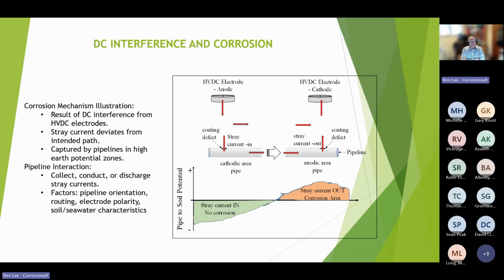And the question is, how does all that cause corrosion? Well, this little drawing, put together by Professor Charalambos, illustrates it very well. It's all down to the coatings on the pipes and the cathodic protection that are there to protect it. The coating is specially prepared for buried pipelines, and it stops the current leaving the pipeline, because where the current leaves the pipeline, you will lose metal. From Faraday's law, we know that 1 amp DC for 1 year will consume 9.1 kilos of steel. And in the old days, we had coatings which fell off in sheets.